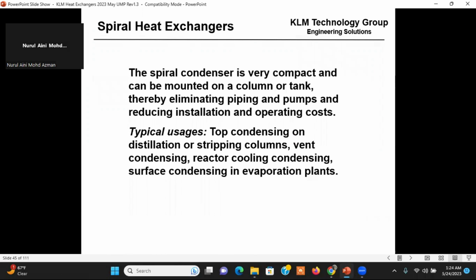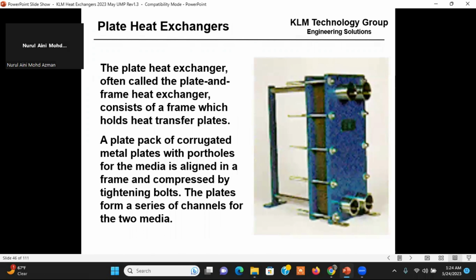Condensing on the top of distillation columns, vent condensing, reactor cooling condensing, surface condensing, and evaporation plants. Plate heat exchangers are plates that are stacked together. You might have one process on one set of plates, and the second process on the second set of plates. And so they have a lot of surface area. Okay, and so we know that the heat transfer is Q equals UA delta T. And so when you have a lot of surface area, you have a lot of A, you get a lot of heat transfer. All right.